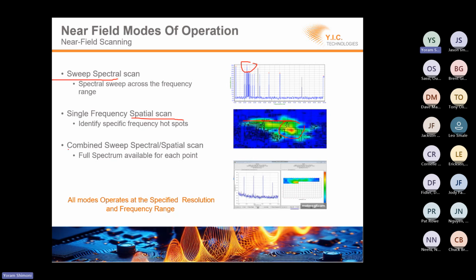The next thing is actually a combination of a sweep, spectral and spatial scan. And the idea here is that usually the user will do that at the end, once he removes or eliminates most of the issues. That will collect a lot of information. In our tools, usually this scan is the slowest, but that will allow the user to collect a wide range of information across the frequency range in a very high resolution, and you can save this information in your database for future use. And again, for records, just to make sure that you did release this DUT as expected.